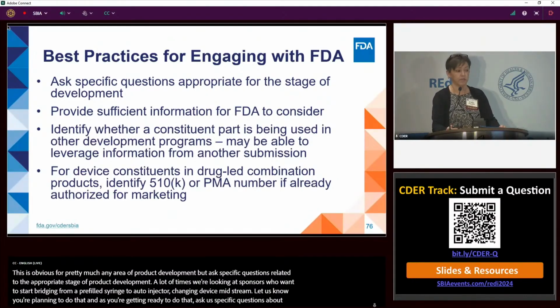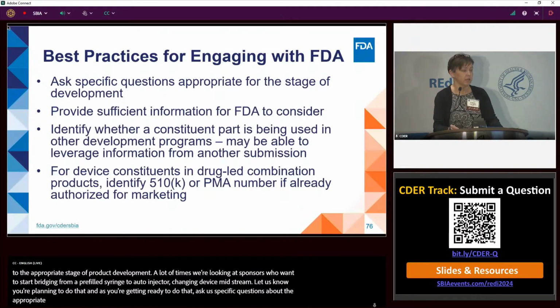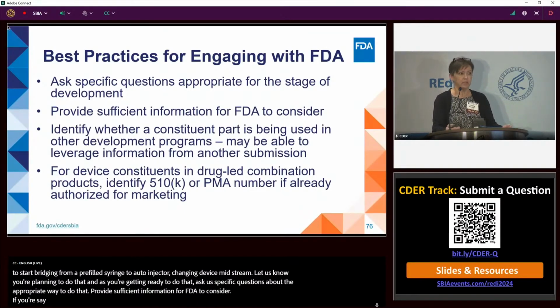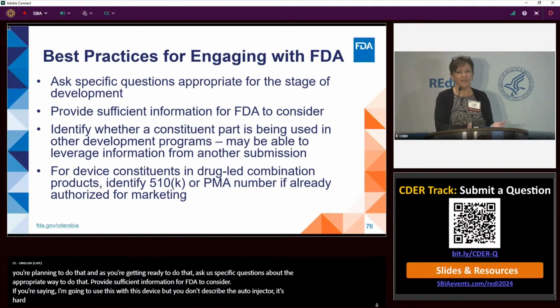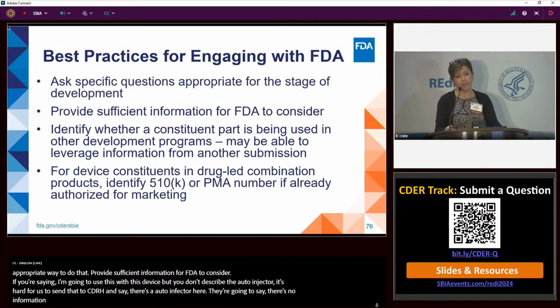Provide sufficient information for FDA to consider. If you're just saying, well, I'm going to use this with this device, this auto-injector, but you don't describe the auto-injector, you don't explain anything about it, it's really hard for us to then send that to CDRH and say, hey, there's an auto-injector here. Can you give us feedback? And they're going to say, no, there's no information. They should do device stuff with the auto-injector, right? So provide us enough information so we can give you constructive feedback.